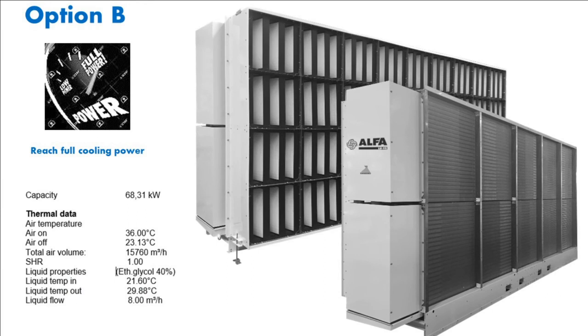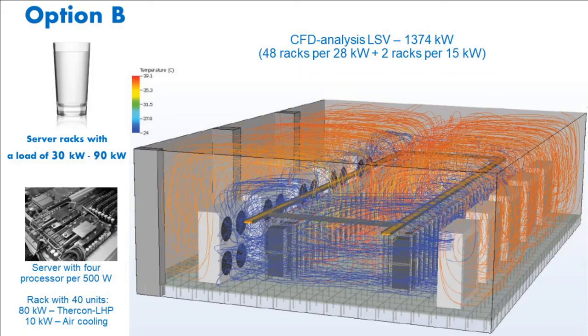Industrial low-speed ventilation air coolers are designed according to the needs of the servers, and due to the large cross-section and large heat exchange area, they provide clear cooling capacity over the entire load range without condensate and with extremely low power consumption of fans. You see the CFD modeling which was carried out by our customer for a hall with 48 racks with an average power of 28 kW, which proves the ability of low-speed ventilation to work with high-density racks.